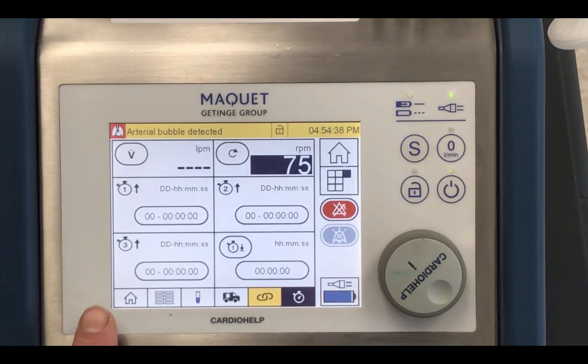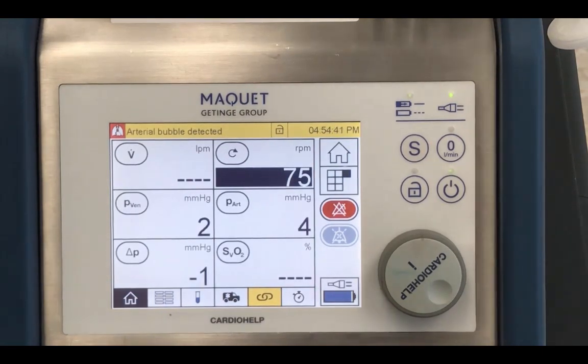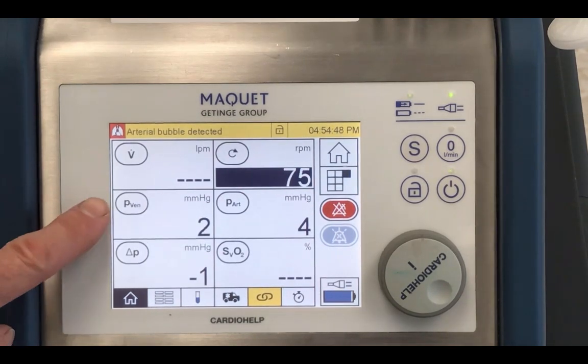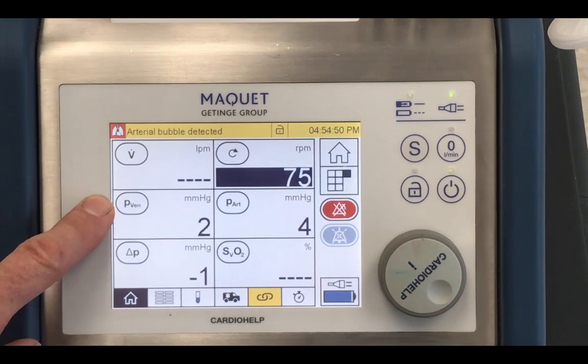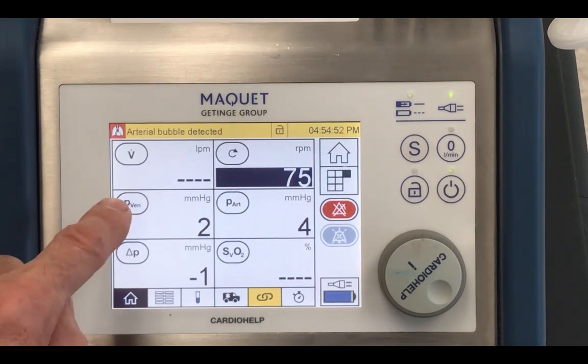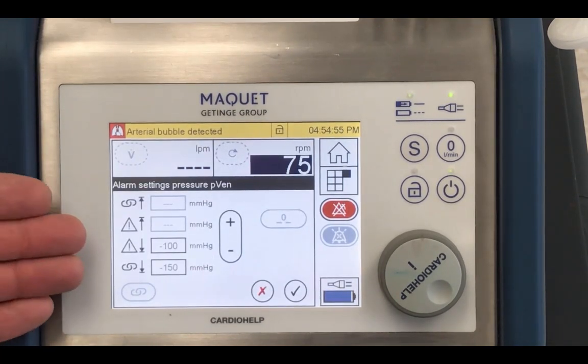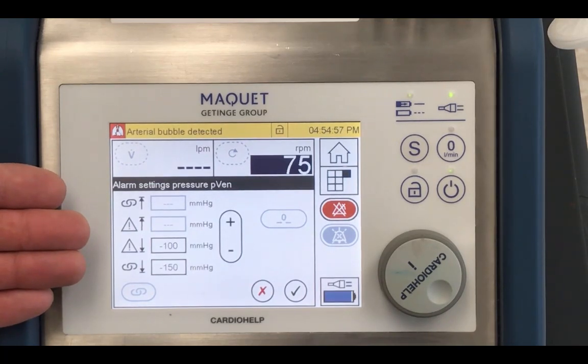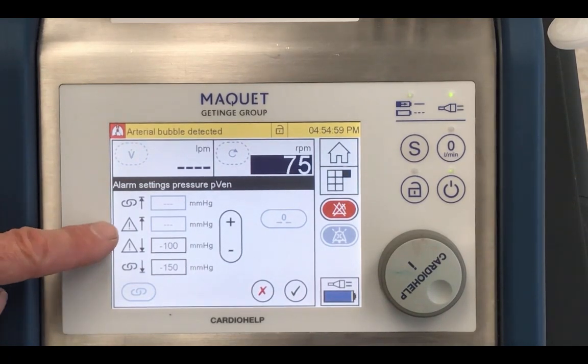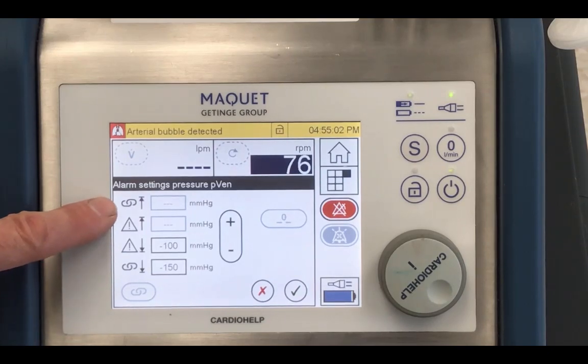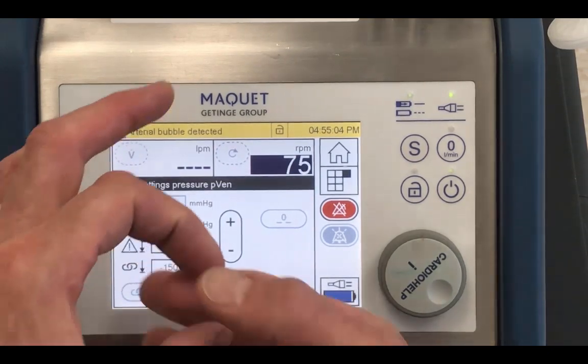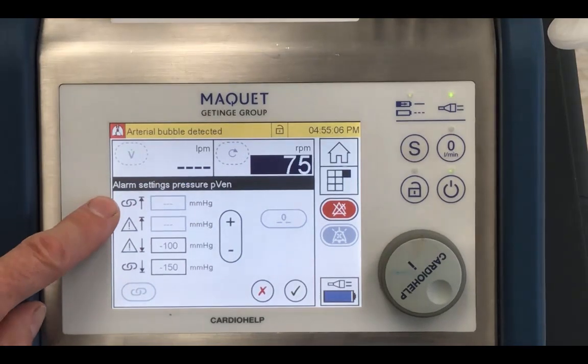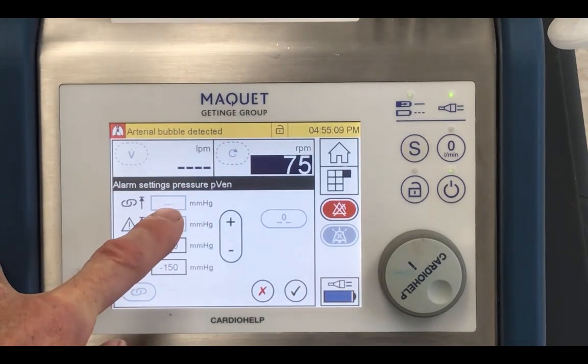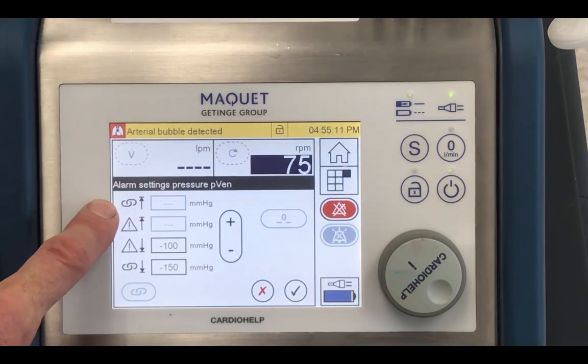Okay, let's go back to the home screen and set some parameters around these variables. Let's say, for instance, we wanted to set some limits on the venous line pressure. So we're going to press this button here to go into this menu, and it's going to take us to the venous line pressure alarm settings, and we can tell it when we want an alert and when we want an intervention set. That picture of the interlocking links is when you have the data you put in there, that's going to trigger an intervention.